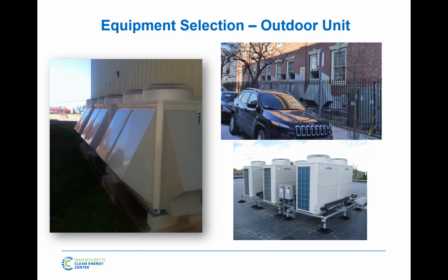When looking at equipment selection, here are some pictures of different outdoor units. I'd like to give people an idea of what you have to keep in mind when you're looking at a building. You're going to need to locate equipment somewhere. This bottom picture is probably the clearest that shows the outdoor units. This is about 40 tons worth of equipment, all on a roof. This one's on a snow stand, which we recommend for anything in the Northeast.